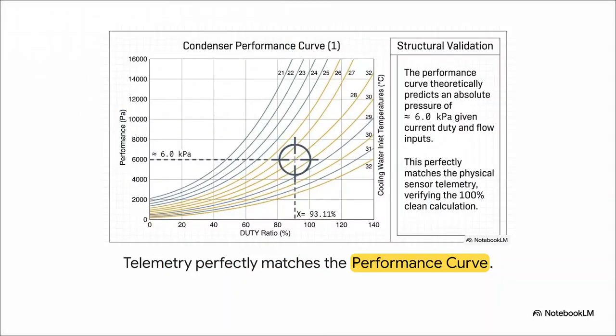To really validate this, let's map our math onto the manufacturer's actual condenser performance curve. If you take our duty ratio of roughly 93% down on the x-axis and trace it up to our cooling water inlet temperature curve of roughly 28 degrees, the intersection theoretically predicts an absolute pressure of about 6.0 kilopascals. And what did our physical sensor telemetry read earlier? Exactly 0.060 bar, which is exactly 6.0 kilopascals. The theoretical physics and the physical sensors are in perfect alignment. You love to see it.